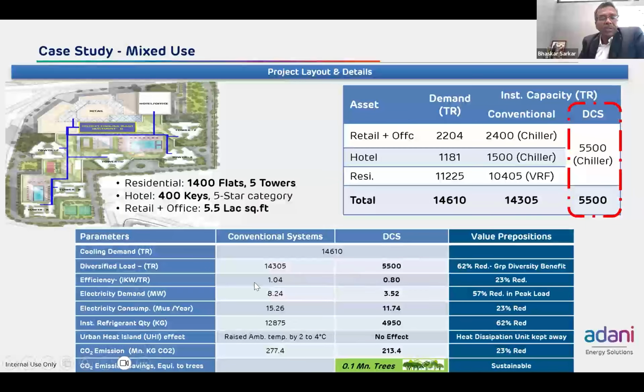electricity infrastructure. The conventional systems have an efficiency of 1.04 on a very optimistic, first year basis, whereas the DCS has 0.8, which is 23% less. This actually impacts the electricity demand also, which is significantly less. The electricity consumption is also significantly less because of the efficiency. The refrigerant capacity is also 62% less because of the lower capacity.